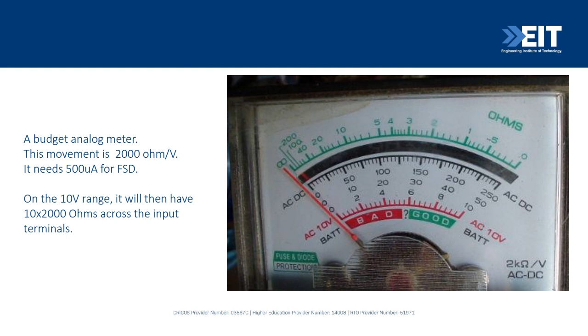This is a mirror, not bad for a budget meter. You know why it's here? There's a red reflection visible. When measuring with this sort of meter, you mustn't see that reflection. The needle must sit right on top of it, so you know your eye is exactly above the correct measurement. Right now we're off to the right-hand side, so it won't read correctly. The mirror isn't for checking your eye, it's to get an accurate measurement.